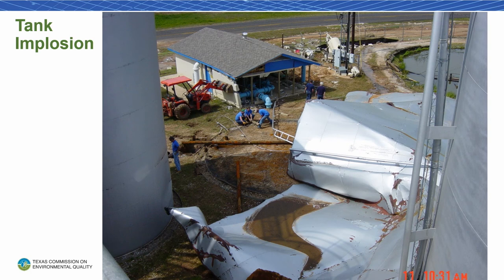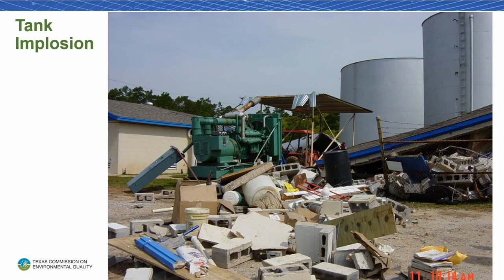The reason I put this in here is during Winter Storm Uri, there were some vents that were completely iced over. The vent on top of a storage tank - when the high service pumps pull suction on that tank, and the vent is clogged or blocked by ice formation, this can occur. Now in this situation it wasn't ice - it was that they had pigeons nesting there or whatever, they weren't maintaining this tank, and the vent was not breathing. So when the pumps pulled suction on that storage tank, it just collapsed like a can. That's what it did to the pump building.